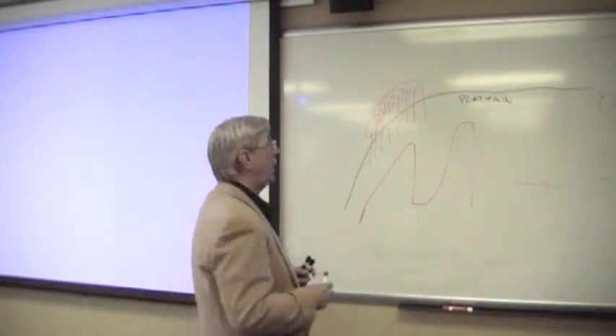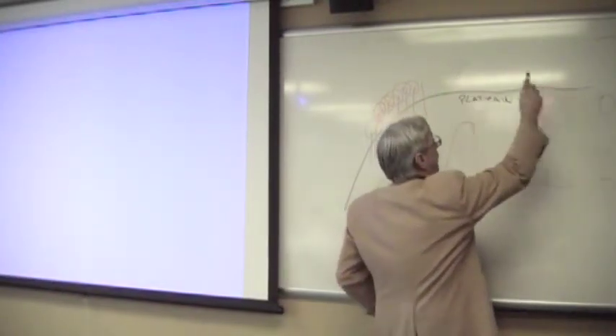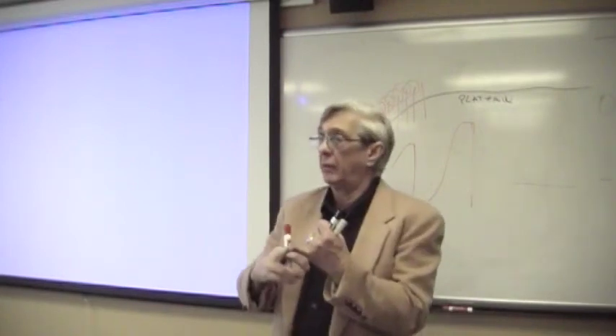Is the machine waiting until that slope levels off before it spits out a number, or is it doing it in real time? These calculations are going on as the person is blowing. When does it say, okay, I like this? Well, that's when you get to the point where this reading is stable, the rate of increase is no greater than 0.02, and the person stops blowing. It's going to accept the sample.